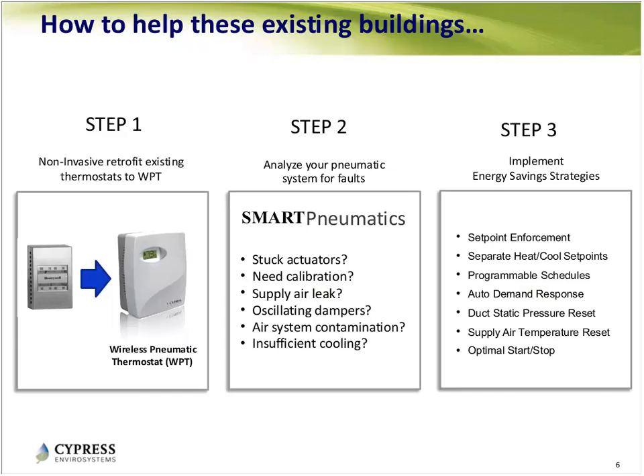Second, once those intelligent thermostats are in place, they collect a lot of data, and we can run analytics to detect faults in the system. Some faults, like a stuck actuator or a leak, may have existed for years without anyone knowing because there was no data. Once you upgrade to digital thermostats, the smart software goes through all the data points and identifies faults that need fixing, allowing you to retro-commission your building back to optimal function.